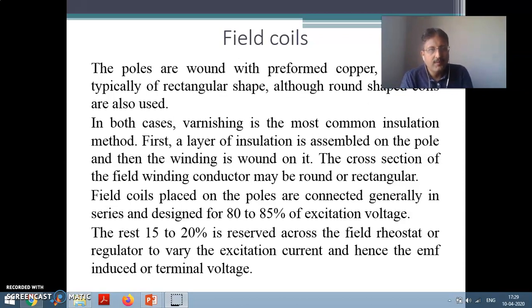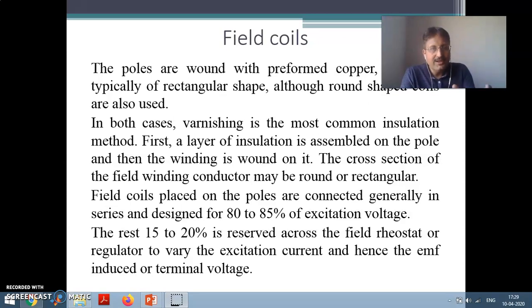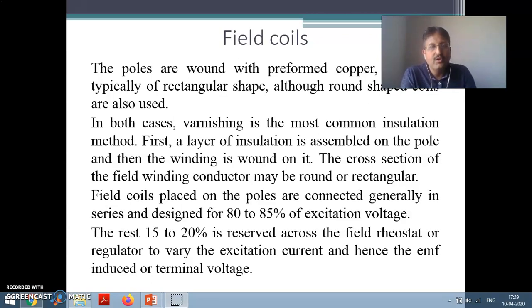Field coils placed on the field poles are connected in series with each other, and they are designed for 80 to 85 percent of the excitation voltage because the remaining 15 to 20 percent of the excitation voltage is across the field regulator or field rheostat. The field rheostat is connected in series with the field, and its function is to control the field current, hence control the flux. Control of flux will control the voltage if it is a generator, and speed if it is a motor.